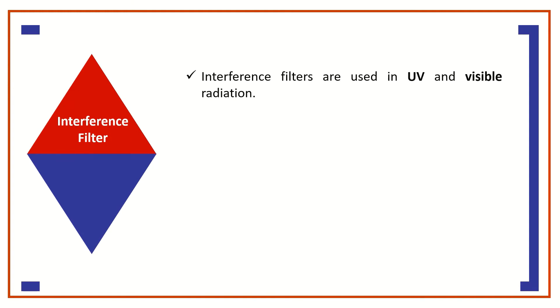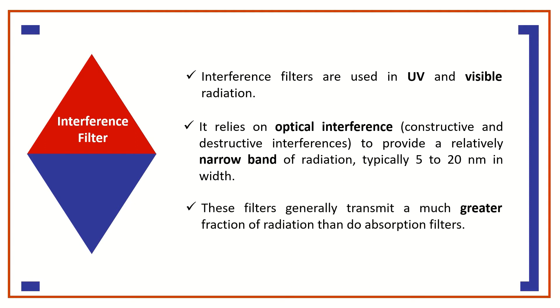Interference filters are typically used for absorption measurements in UV and visible radiation. As the name implies, an interference filter relies on optical interference — that is, constructive and destructive interferences — to provide a relatively narrow band of radiation, typically 5 to 20 nanometers in width.